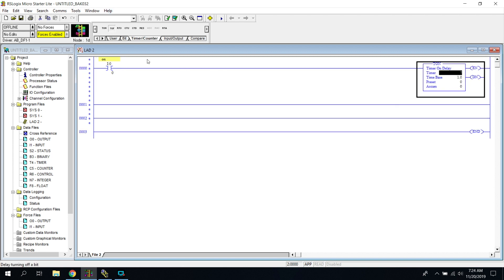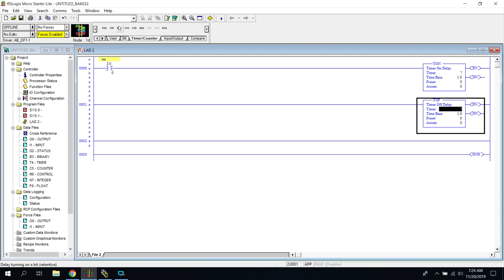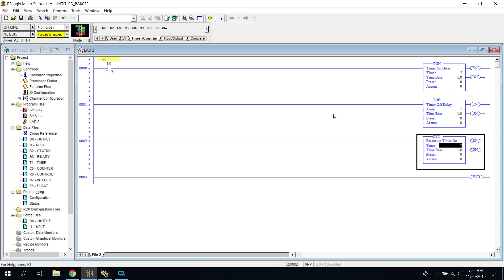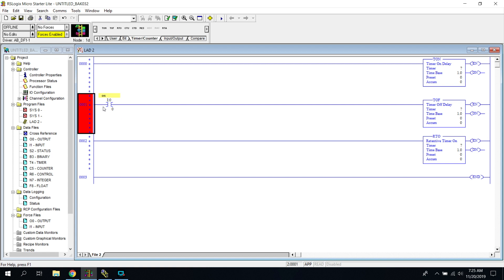We have a timer on delay, a timer off delay, and a retentive timer. A timer on delay will turn on when the rung becomes true — so when I press this button, the rung becomes true and the timer will start. With a timer off delay, when I release this button and it goes from true to false, this timer will start. There are some different output bits that do different things, which we'll get to in a minute.